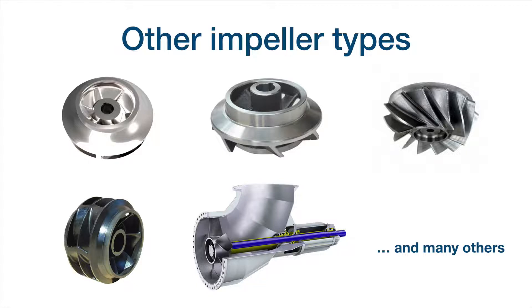The main thing to understand how a pump behaves — the most important classification — is the division into radial impeller, mixed-flow impeller, and axial impeller, based on the direction of the flow through the impeller. This is the main division of impellers. From this starting point, you can find many different types of impellers for different applications, but equations will be applicable to this classification of radial, mixed-flow, and axial type impellers.